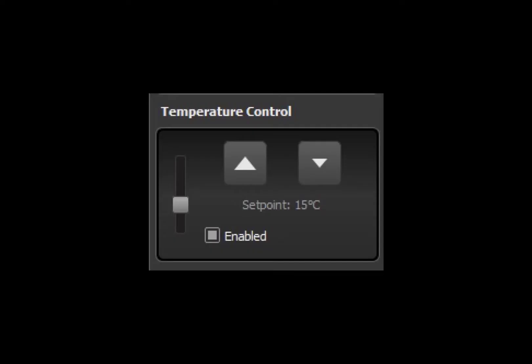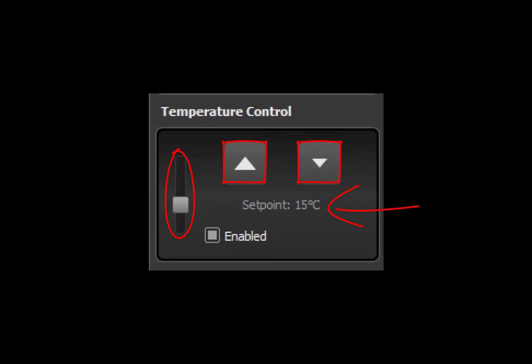Lastly, temperature control allows the user to configure the set point or desired target temperature in Celsius of the detector's thermoelectric cooler or TEC. Different spectrometer models support different operating ranges with optimal set points, so the temperature control is automatically range-limited to the correct temperature range for any spectrometer. This means that the TEC can't be overdriven in either direction. Generally, detectors that are thermoelectrically cooled to lower temperature are capable of detecting fainter signals since they generate less thermal noise and are able to maintain a lower, steadier baseline. The user can set the set point by using the up and down arrows, slider, or editing the numeric field to the desired value.